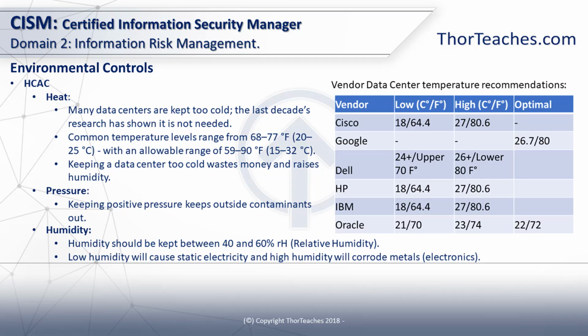Most vendors have set ranges for their equipment where it should be operated in the optimal conditions, and it ranges somewhere between 68 and 77 Fahrenheit or 20 to 25 degrees Celsius. They also have allowable ranges. That's where the equipment is going to continue to function, but it's not super good for the equipment. It will deteriorate faster and not work optimally. Those ranges are between 59 and 90 degrees Fahrenheit and 15 to 32 Celsius.